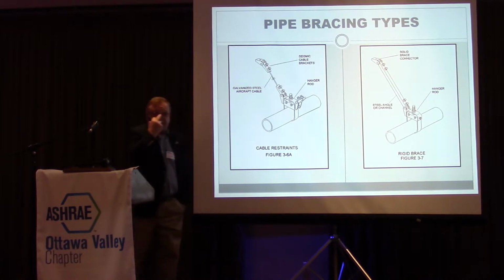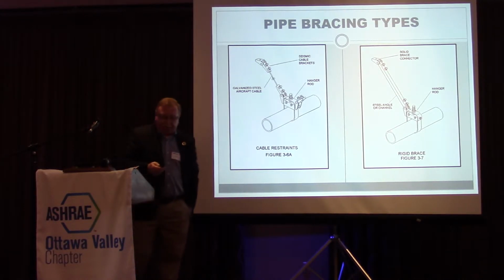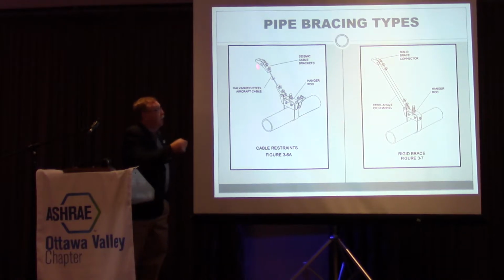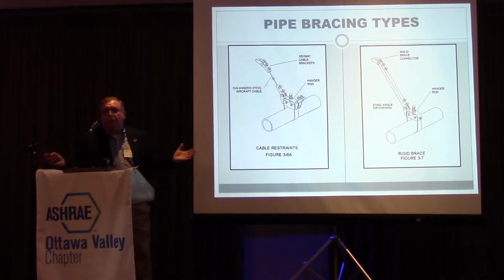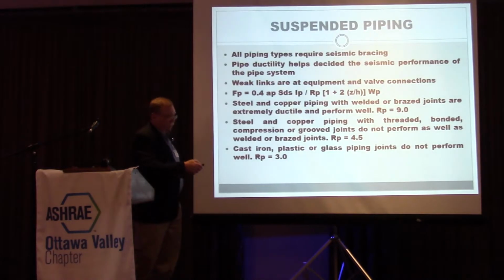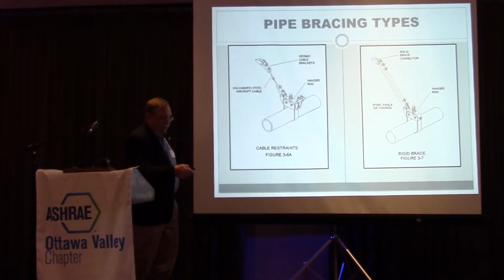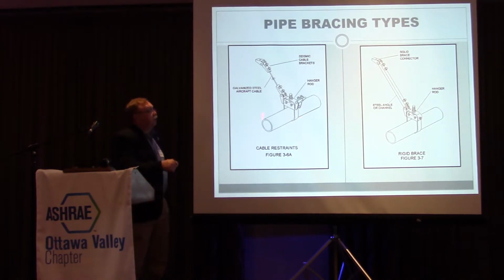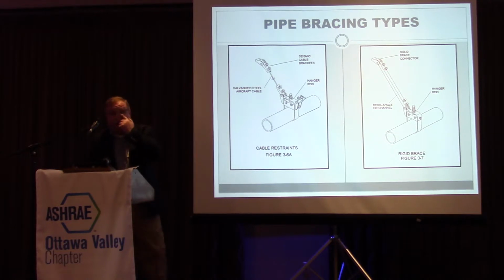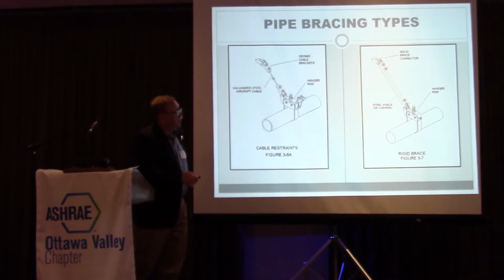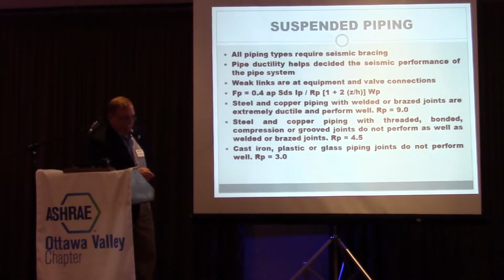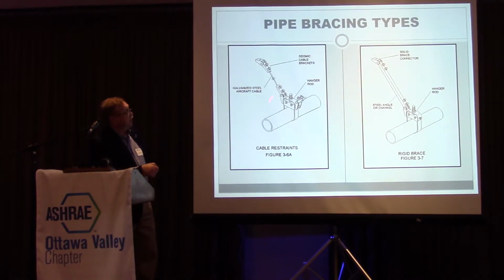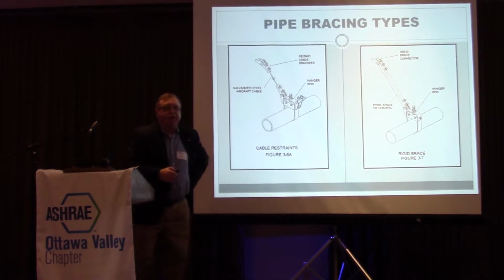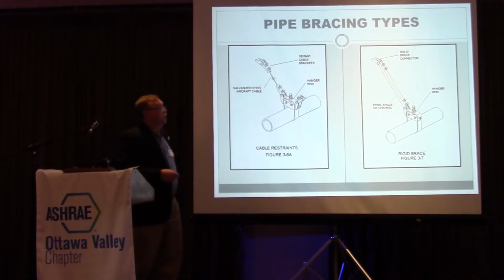You've got 2 basic types of bracing used in the mechanical world: cable bracing, which goes off both sides of whatever it is, and a rigid brace. The difference is: you'd typically use cable bracing for something that is vibration isolated, and rigid bracing when it's not isolated. You can use cable bracing even when it's not isolated, but you can't use a rigid brace when you've got vibration isolation, because it'll deteriorate the isolation.